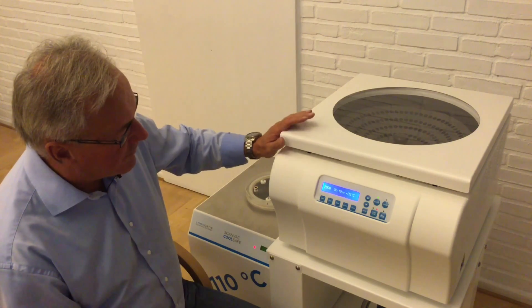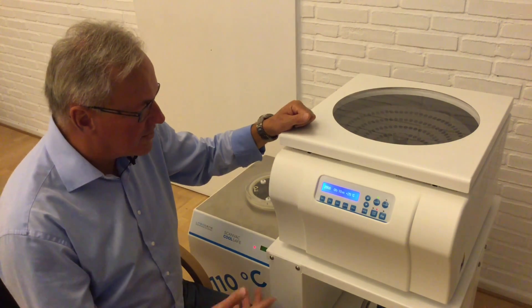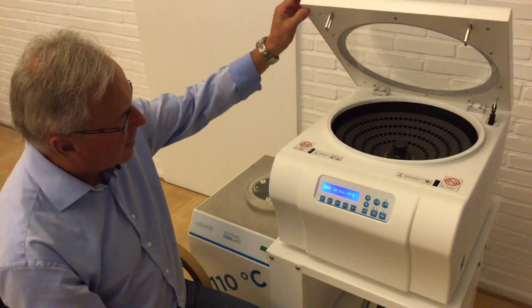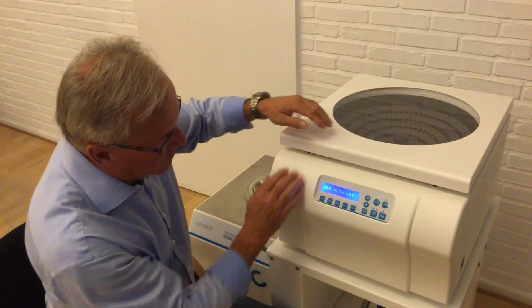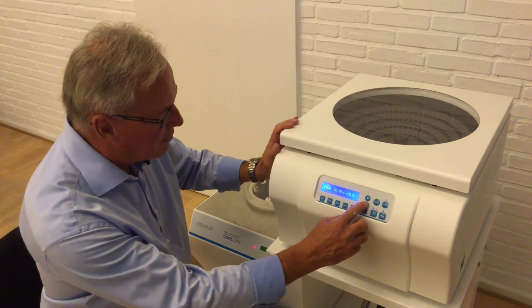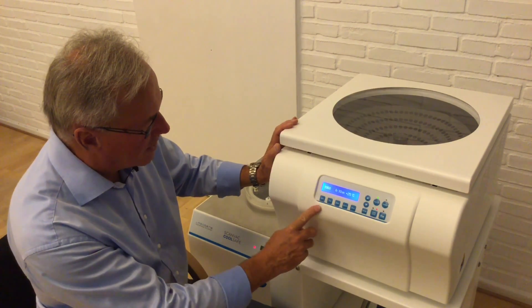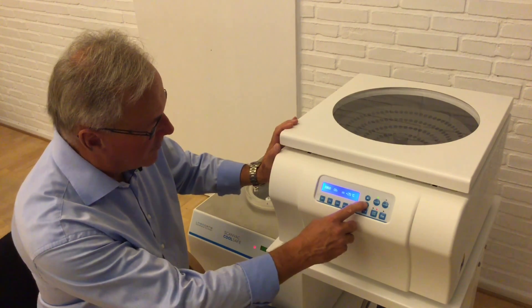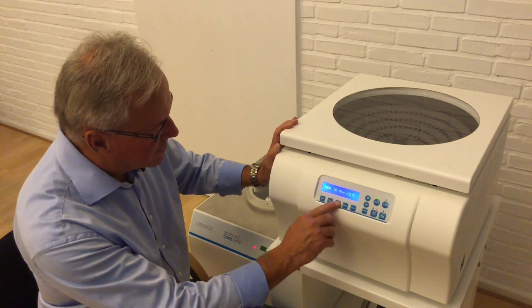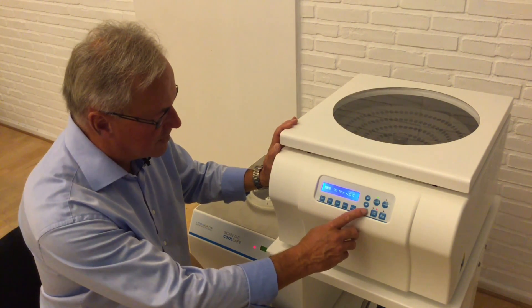The Scan Speed 40 has a display with different buttons which we can use to change set points. We can start the operation and we can open and close the door. Open the door — it is easy to do when the rotation of the cabinet is off. Close the door and the red light goes off. Then we can see the RPM. We can change the set point up and down and press enter. Now we have changed the set point. The time we can change as well, and then we can change the temperature to whatever we like. But it cannot go below the ambient temperature — it is not possible.